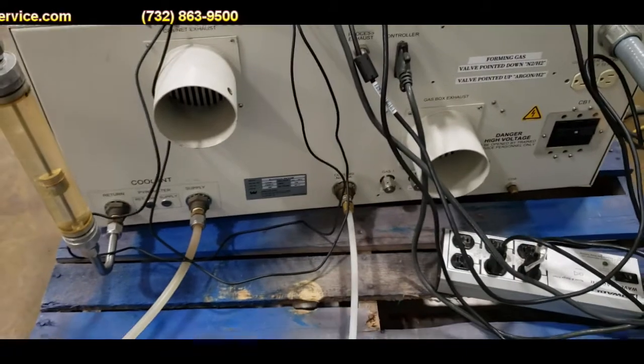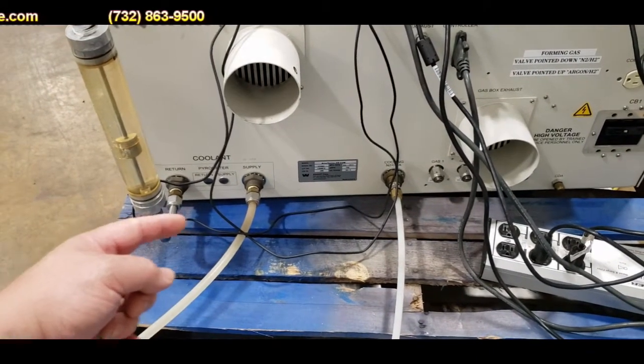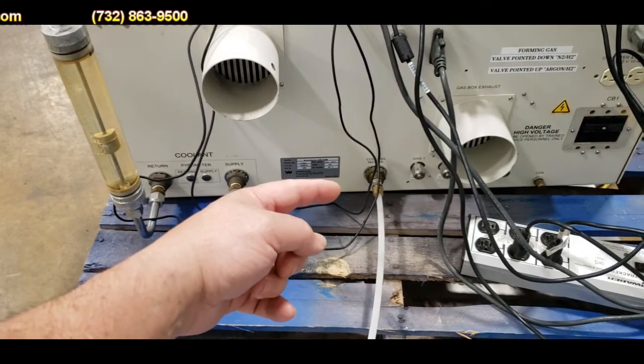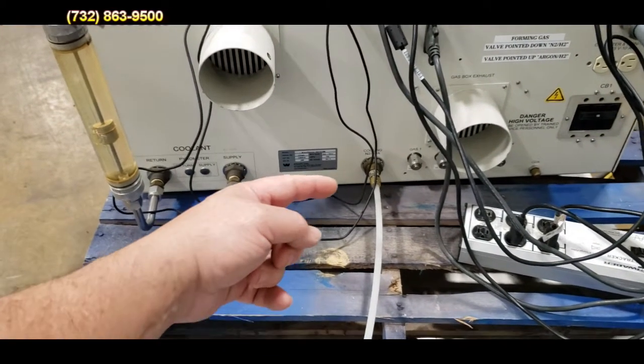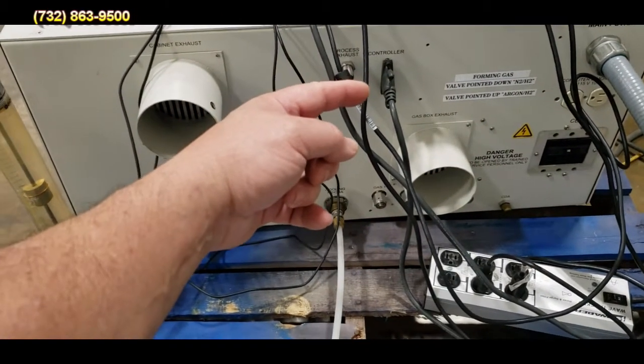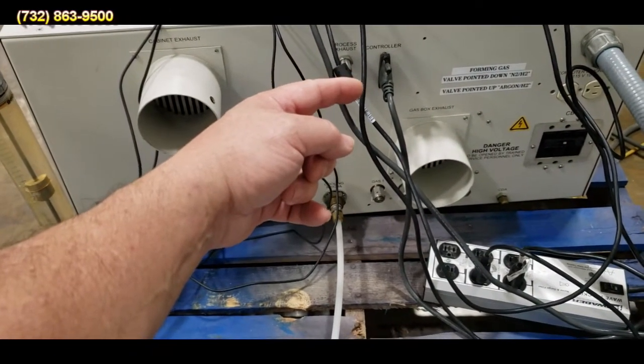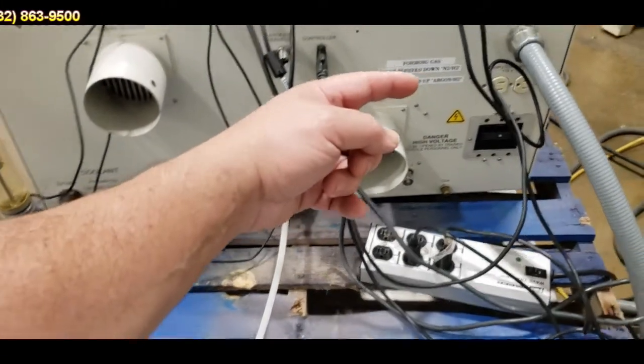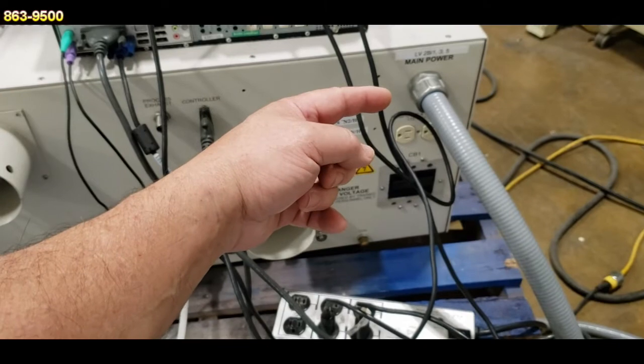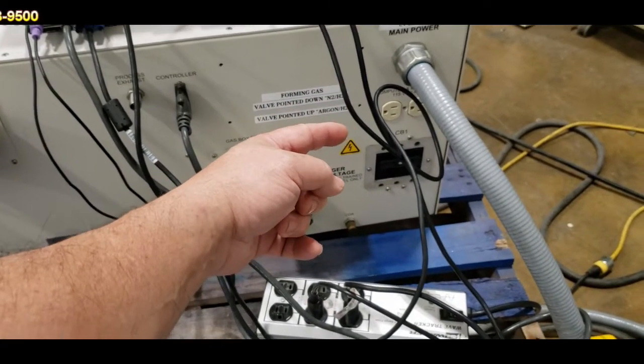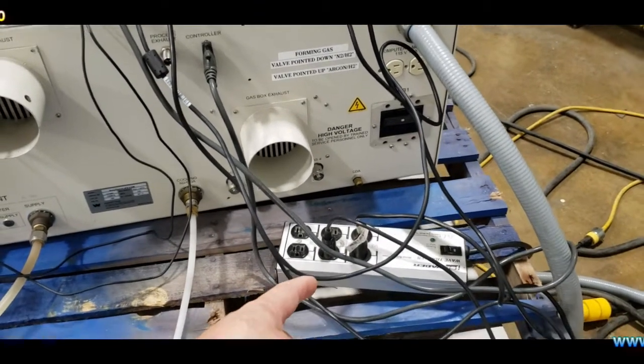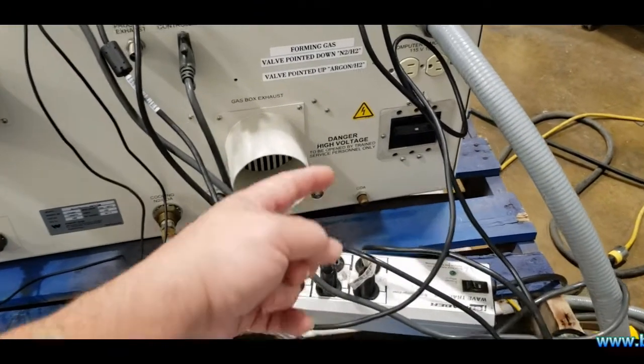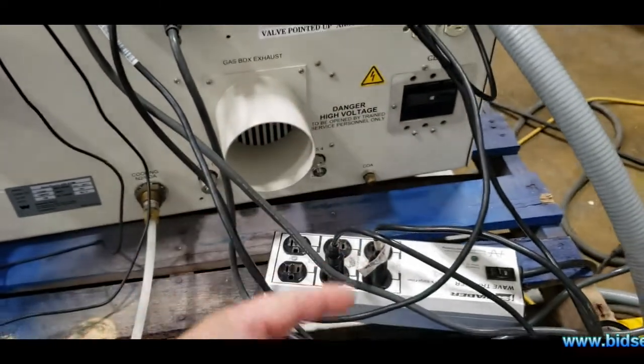In the back here you have your two water lines. You have compressed dry air here to help cool the chamber. Up here is your controller RS-232 hookup. You have your main power right here. A couple power cords to hook up your computer to. I am using a power strip at the moment. You have your main breaker right here. It is a 100 amp breaker.